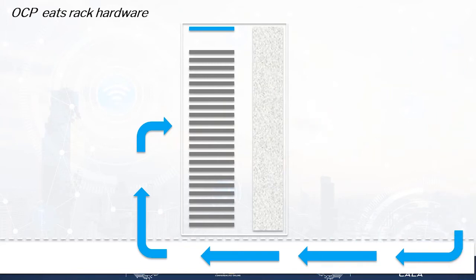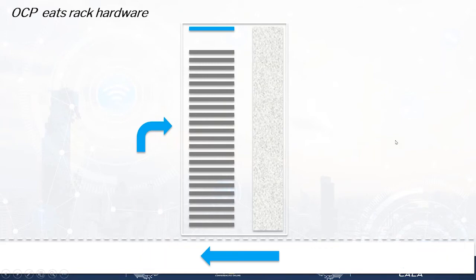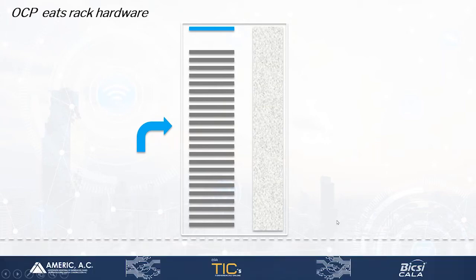We don't use the downflow CRAC units because we don't have mechanical chilling anymore, we don't need it. Therefore, we don't have the air passing under the access floor. This dotted line on the bottom is an access floor. We can take the access floor away because we don't use it. You can put these OCP racks on an access floor, but why do it when you don't need it?